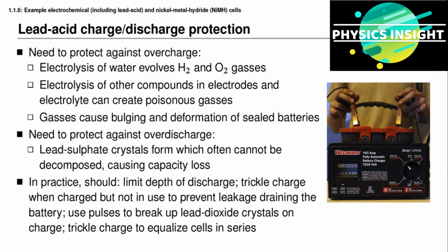they could. But because it's possible to trickle charge a lead-acid battery, if I continue to charge when one cell is at the top, it simply remains at the top and the other cells slowly come up and balance with that top cell. And so trickle charge is very practical, very important in a lead-acid battery cell.